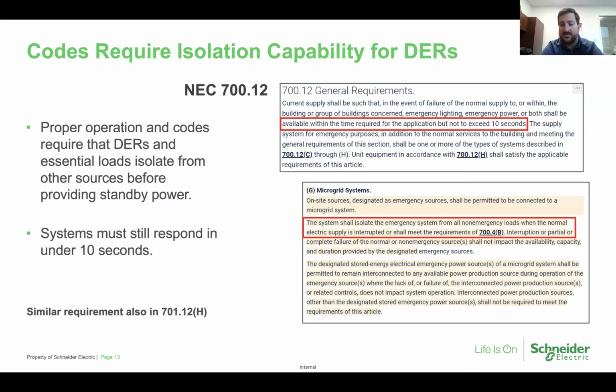So the code goes out and makes sure that people are aware that isolation is a requirement, which is very similar to transferring when you have transfer switches with the generators. The main difference being that when you have a transfer switch, you're always isolating the generator from the utility. But in this case, with isolation devices and interconnect devices, it means the same thing. You are actually paralleled with the utility until the moment you need standby power. In that case, it isolates the inverter-based source and those critical loads.